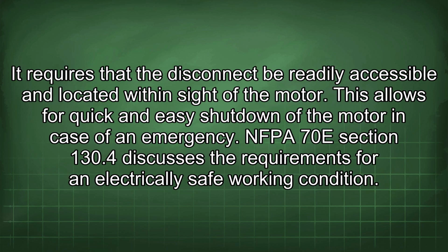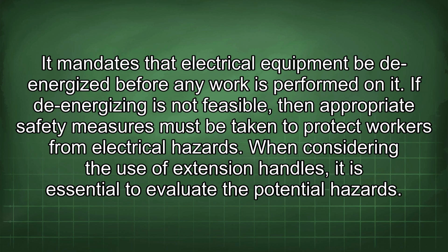It requires that the disconnect be readily accessible and located within sight of the motor. This allows for quick and easy shutdown of the motor in case of an emergency. NFPA 70E Section 130.4 discusses the requirements for an electrically safe working condition. It mandates that electrical equipment be de-energized before any work is performed on it. If de-energizing is not feasible, then appropriate safety measures must be taken to protect workers from electrical hazards.